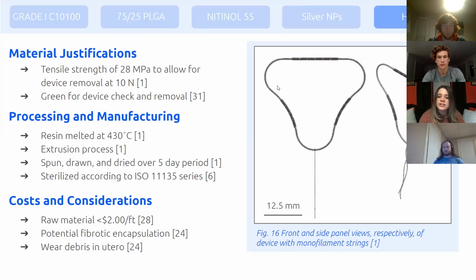They are designed to be checked every year during the patient's gynecology visit, and the neon green string color will be able to contrast nicely to the native tissue, allowing for easier check and removal on the clinician end. The monofilament will be processed via extrusion methods to achieve a diameter of 0.25 millimeters. The polymer will be sterilized with ethylene oxide gas. Similar to the PLGA polymer, however, the polyethylene may provoke fibrotic encapsulation, but because this device is medically inserted using the patient's own anatomy, meaning no incisions are made, we are only anticipating a low to moderate inflammatory response for both of these polymers.